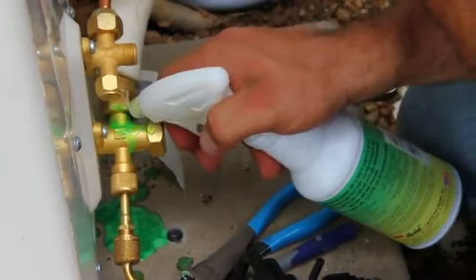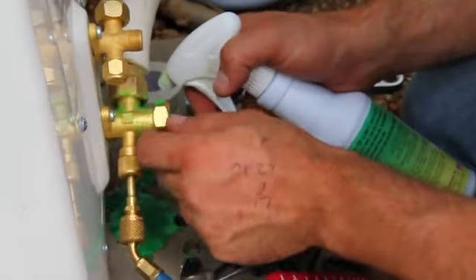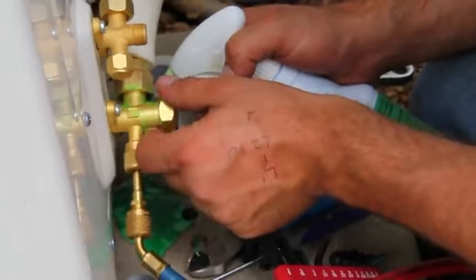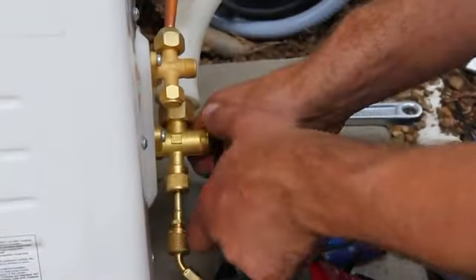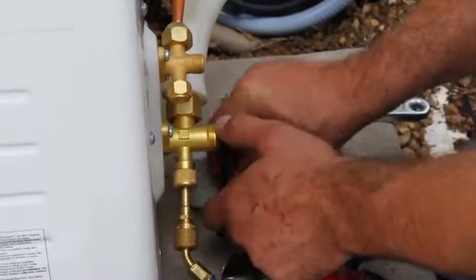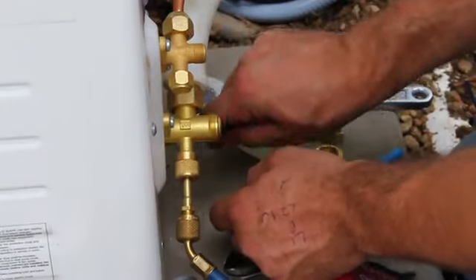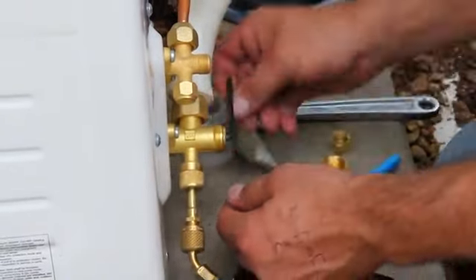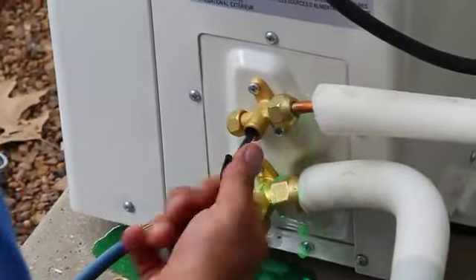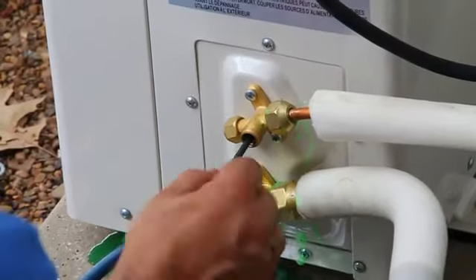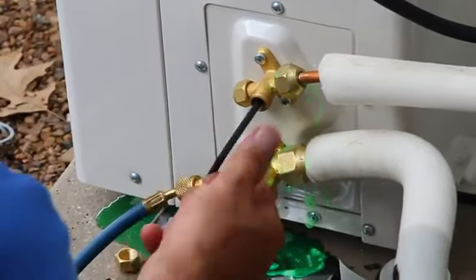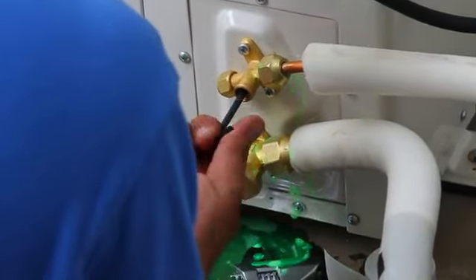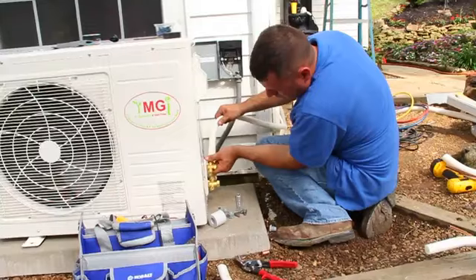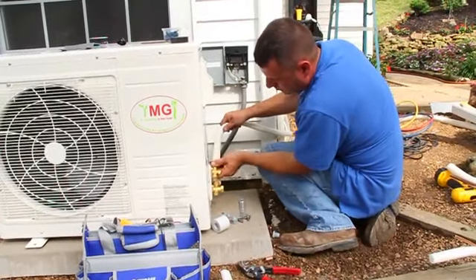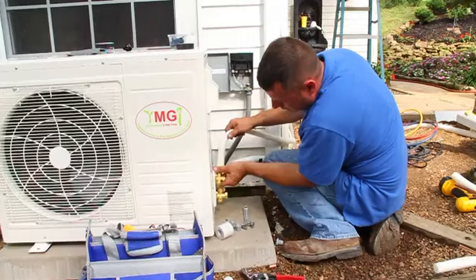Apply a bubble solution to all flare connections. This will help you identify any leaks in the system. Confirm there are no leaks, and then purge the pressurized gas from the system. Next, evacuate the system to ensure there are no further leaks. If the condensing unit does not properly evacuate, then there are leaks, and they must be repaired before any refrigerant is pumped into the system. When you have confirmed there are no leaks, open the refrigerant valves on the condenser.